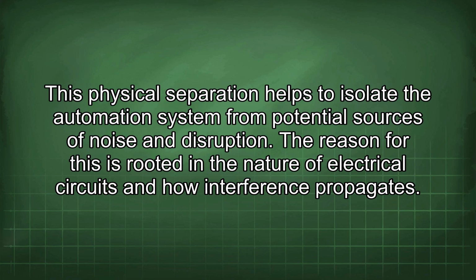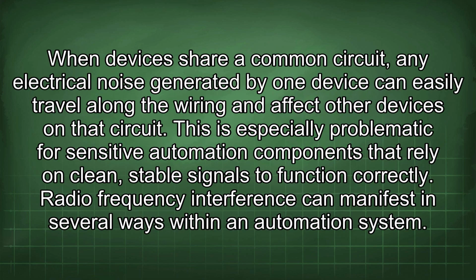The reason for this is rooted in the nature of electrical circuits and how interference propagates. When devices share a common circuit, any electrical noise generated by one device can easily travel along the wiring and affect other devices on that circuit. This is especially problematic for sensitive automation components that rely on clean, stable signals to function correctly.